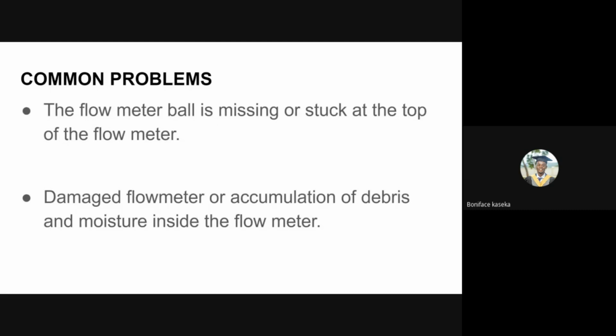This could be due to the accumulation of debris and moisture inside the flow meter. My friend Goodluck explained that when you want to connect a humidifier, you don't connect it at the oxygen source. You need to connect it after the outlet of the oxygen flow splitter. The reason is that if you connect it at the oxygen source, then there will be moisture inside the tubing and inside the flow meter. And when there's moisture and an accumulation of dust and other debris, that will lead to friction. And friction with the ball means that the ball cannot move. That is what we call being stuck at the top.